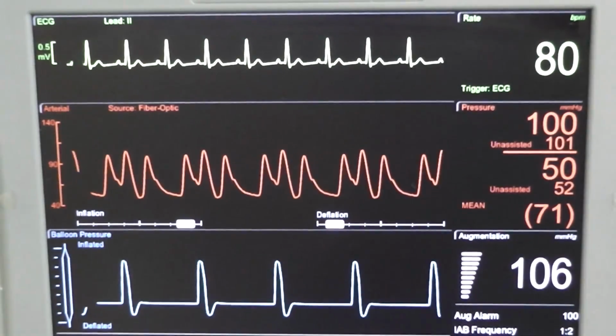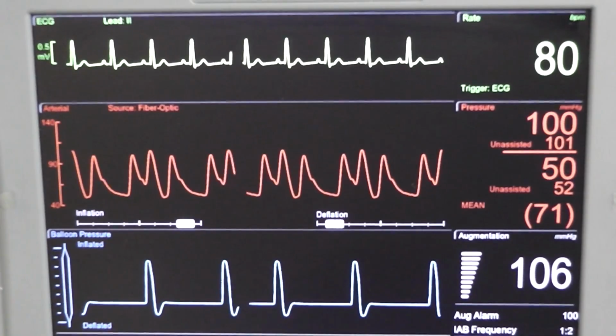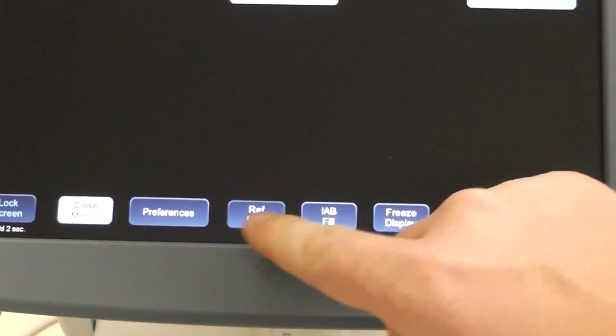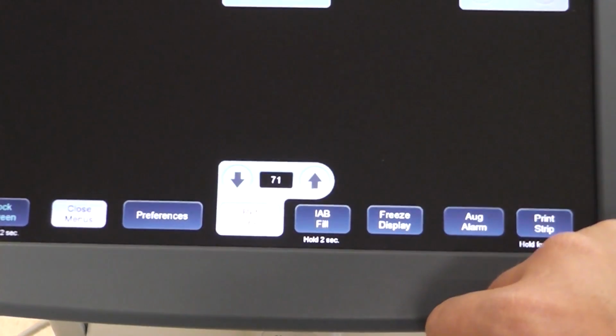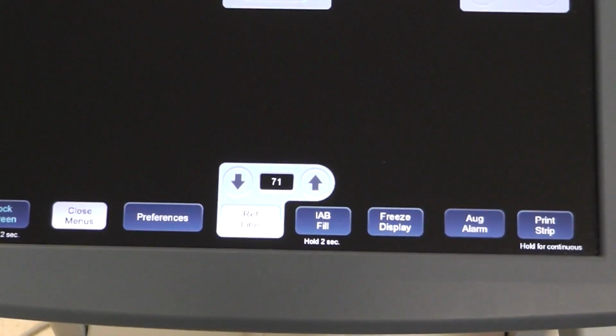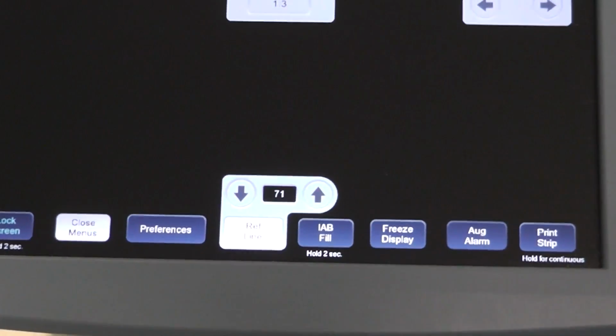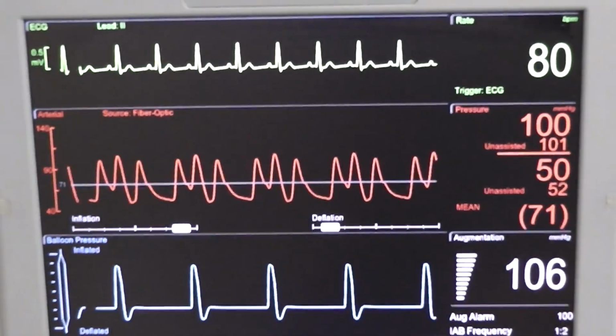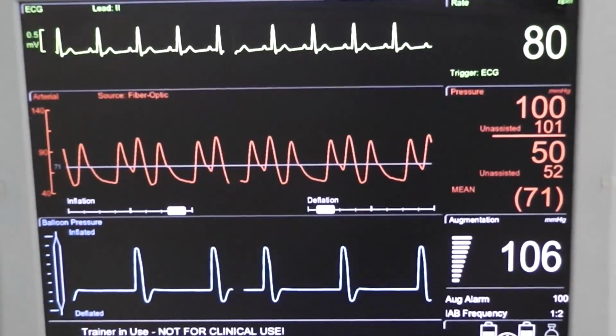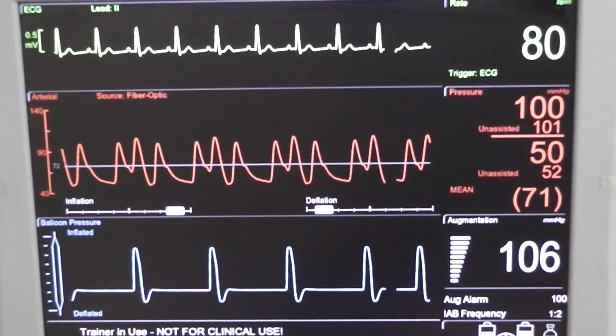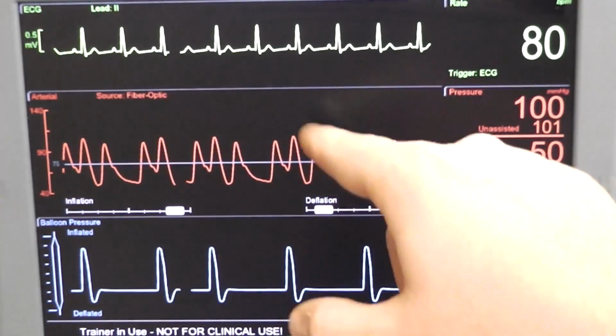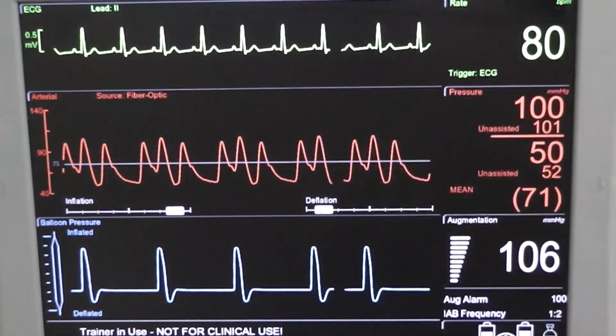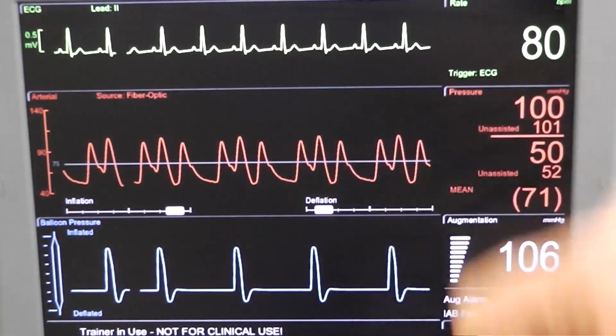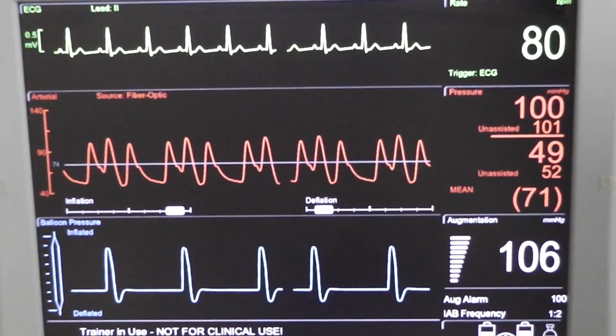Now one thing that we can do to help ourselves with that a little bit is there is a tool on the console called the reference line, which I'm going to use. So down on the console here, there's a ref line button. You can press that, and I'll show what happens up on the screen when you do that. You can move that line up and down. So if I come back to the console here, you'll see now there's this white line that's running across the screen. And if I move those up and down arrows, that line moves up and down. So what I want to do is align that white line with the dicrotic notch. So I'm going to do that.